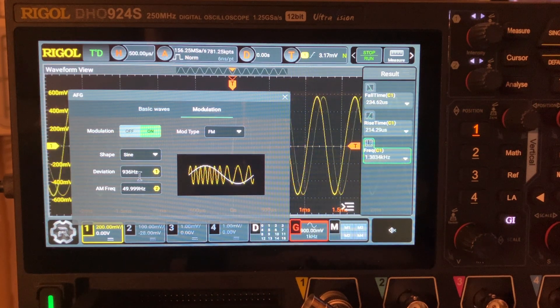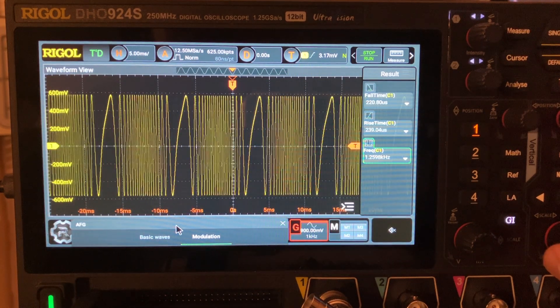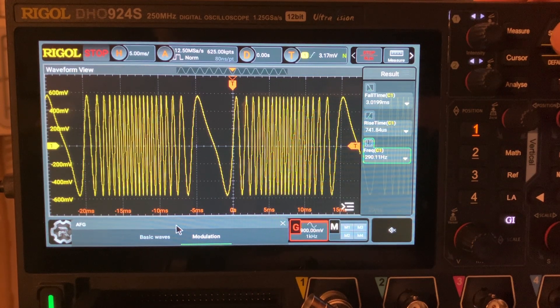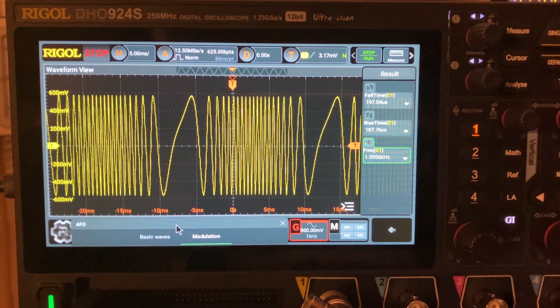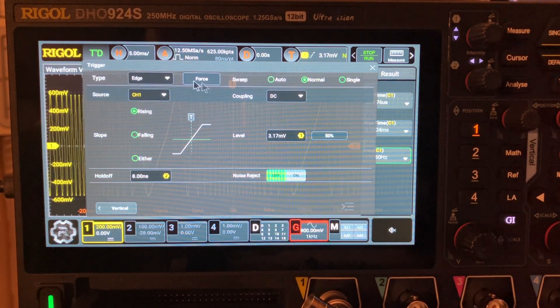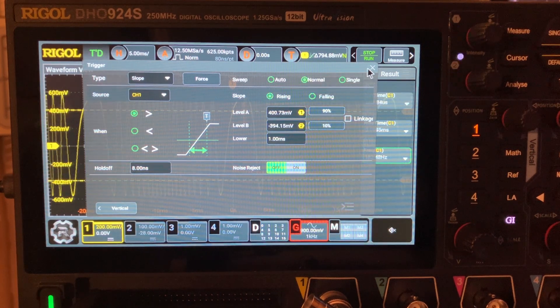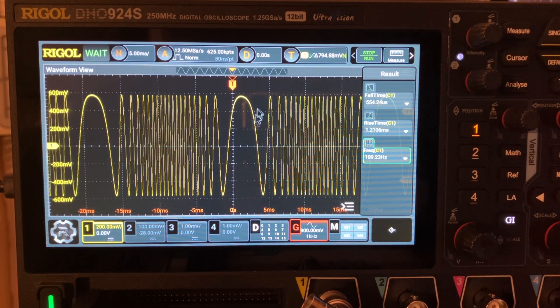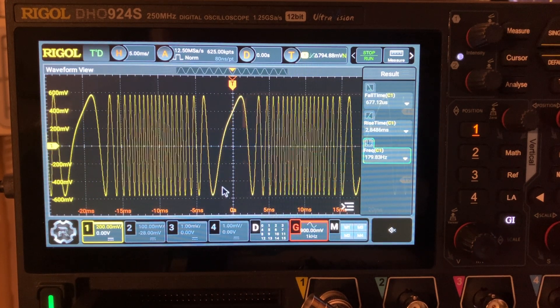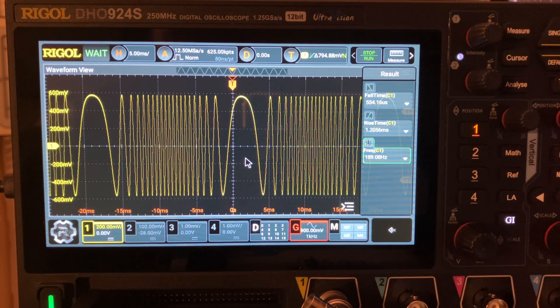Another kind of modulation is frequency modulation. So at one kilohertz, you try to add something that makes sense and this will generate a shape that is a little harder to trigger on. Basically it increases and decreases frequency. It's possible to trigger on it if you use something like slope normal. Let's change the frequency a little bit — it tries to find a place on the waveform where the slope is lower than the rest. This gives you an opportunity to trigger on it — just a trick for frequency modulation. Let's put back the normal trigger.